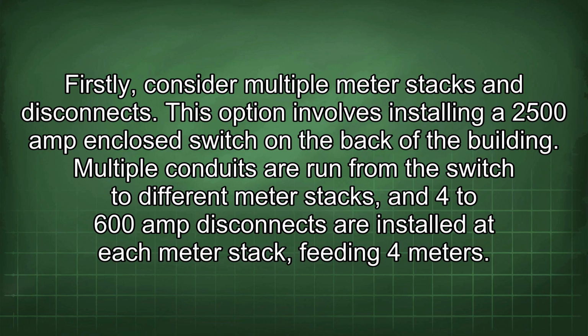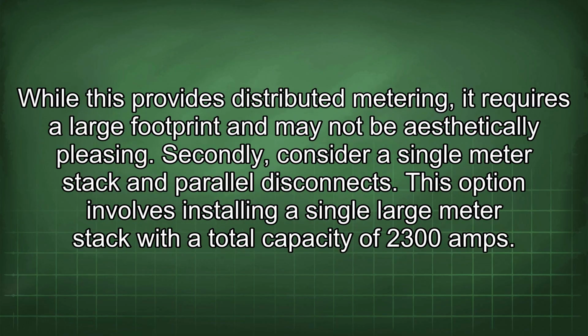This option involves installing a 2500 amp enclosed switch on the back of the building. Multiple conduits are run from the switch to different meter stacks, and 4 to 600 amp disconnects are installed at each meter stack, feeding 4 meters. While this provides distributed metering, it requires a large footprint and may not be aesthetically pleasing.